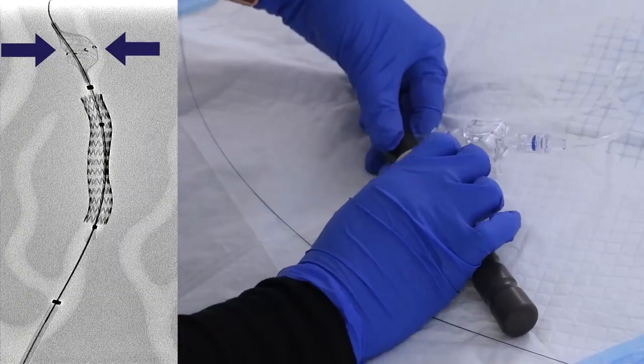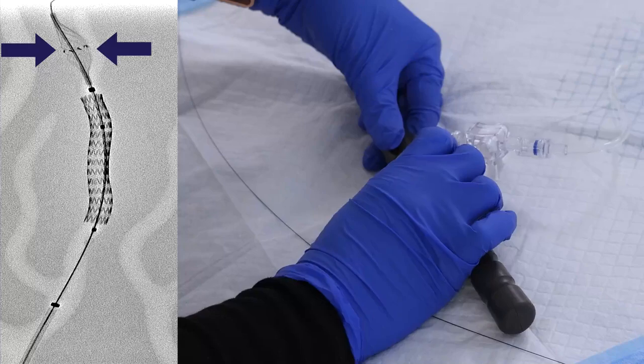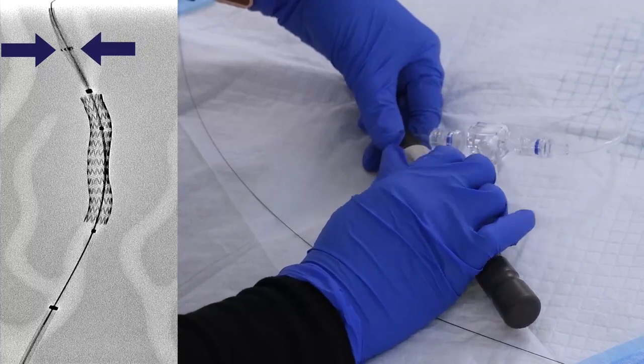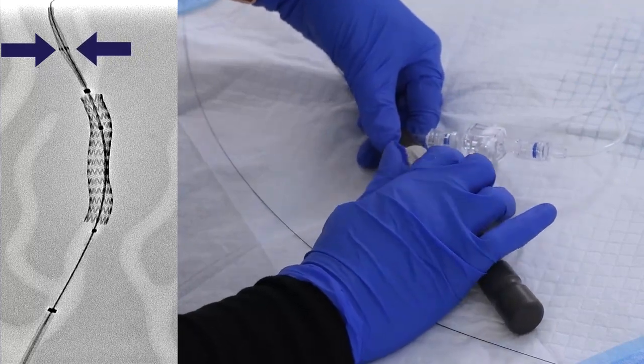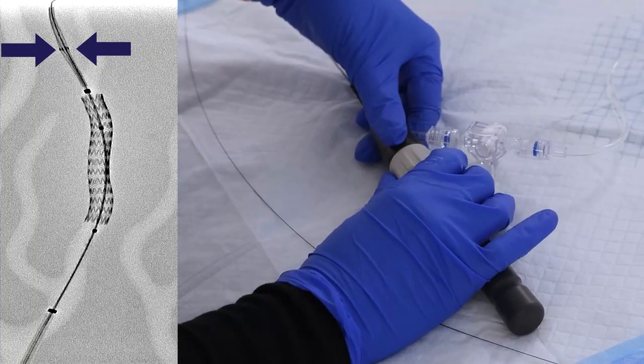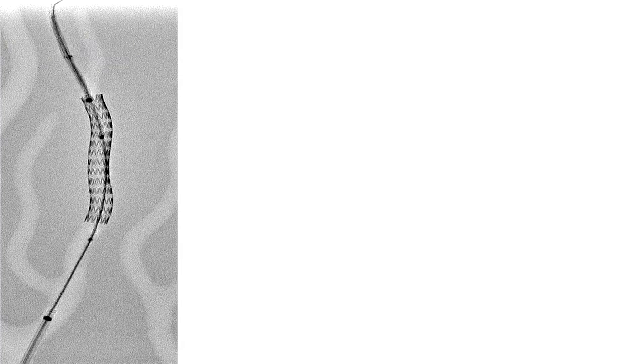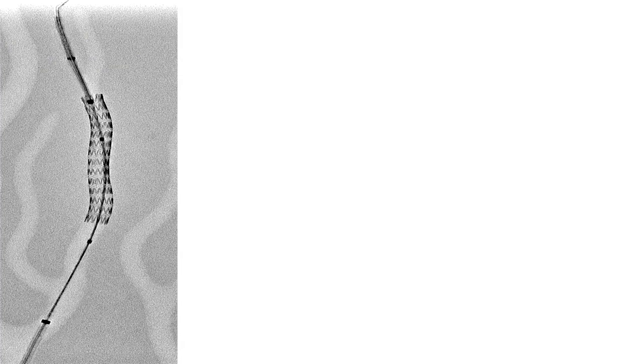Collapse the filter by turning the filter deployment knob clockwise. Continue turning until the handle stops turning. Angiographically confirm that the filter has collapsed using the circumferential filter markers. Withdraw the catheter slowly while preserving guide wire position. Please note, a radiopaque marker is located 1 to 2 millimeters proximal to the catheter tip and can be visualized fluoroscopically during advancement and retraction through the lumen of the deployed stent.